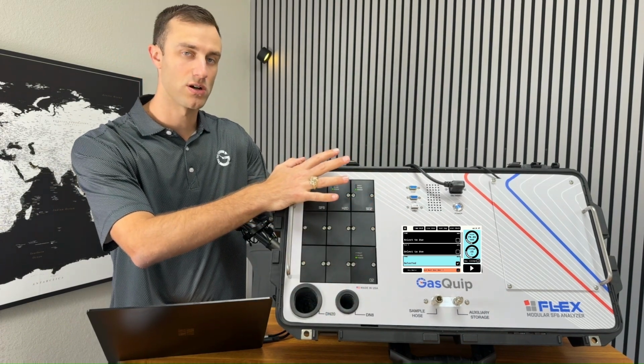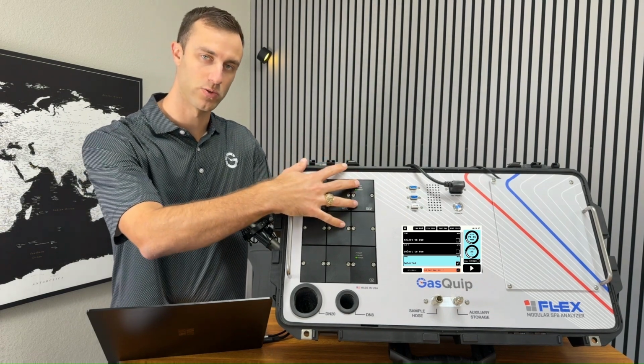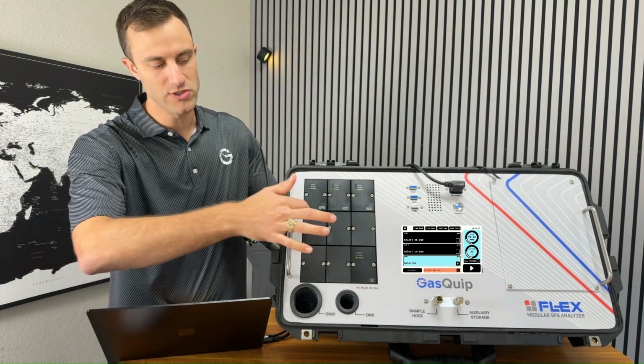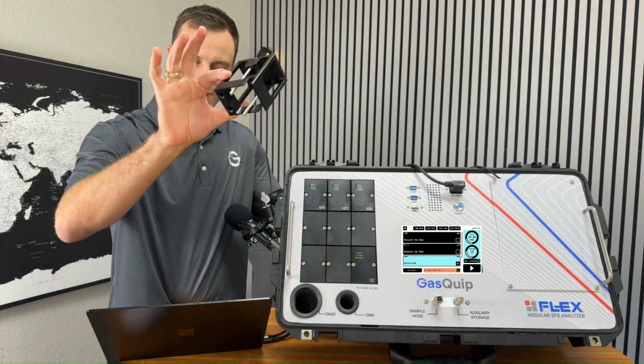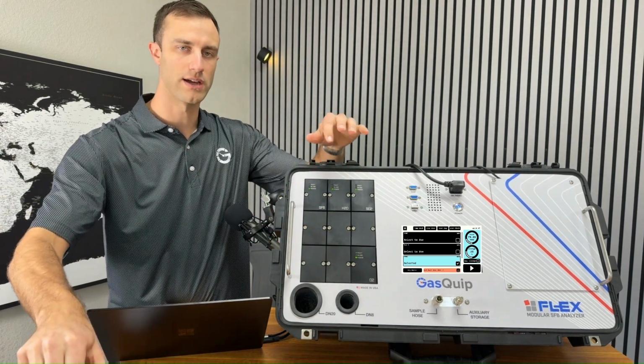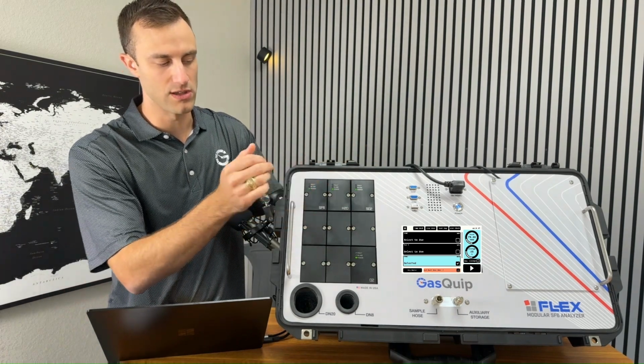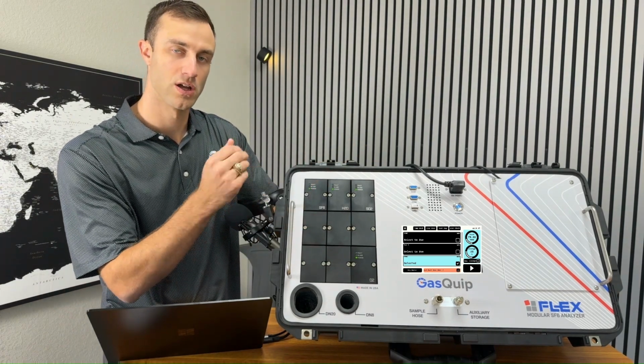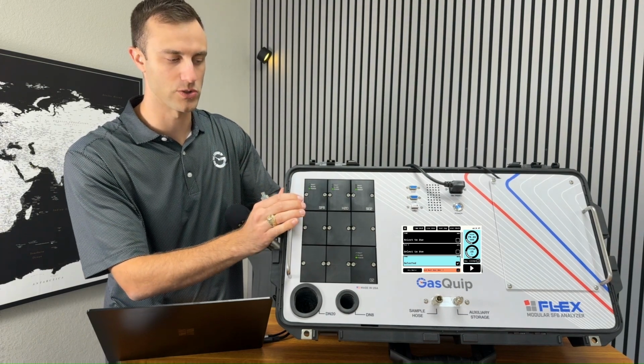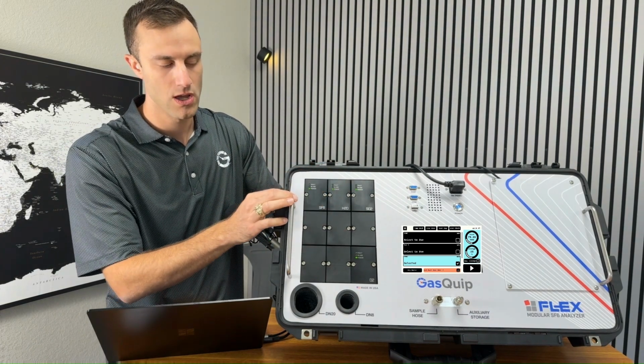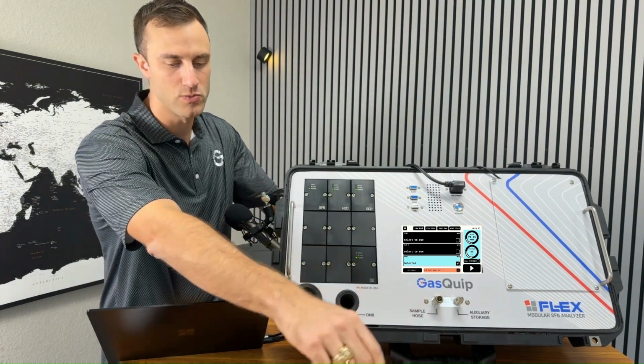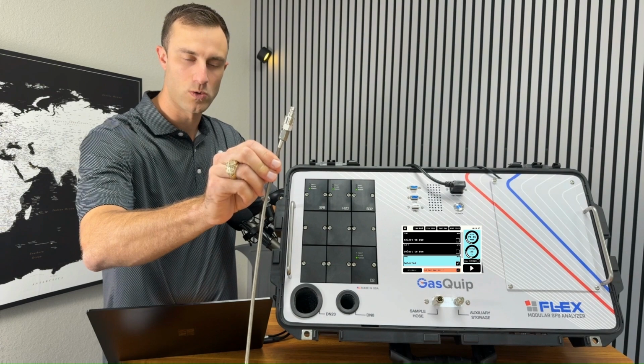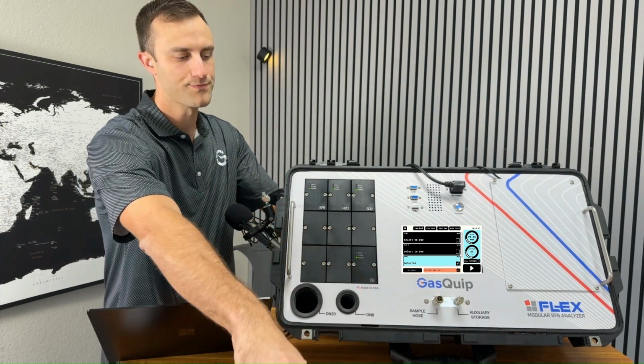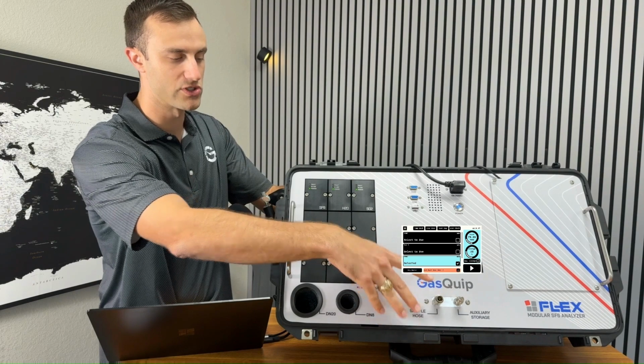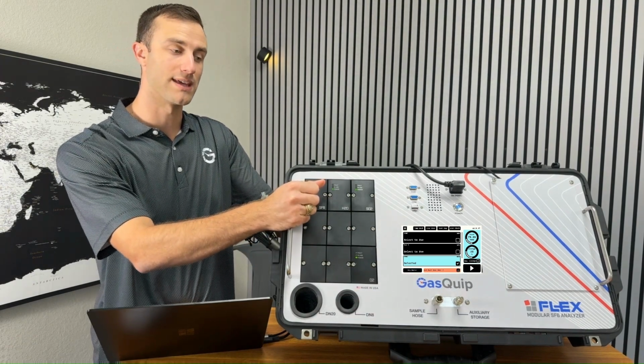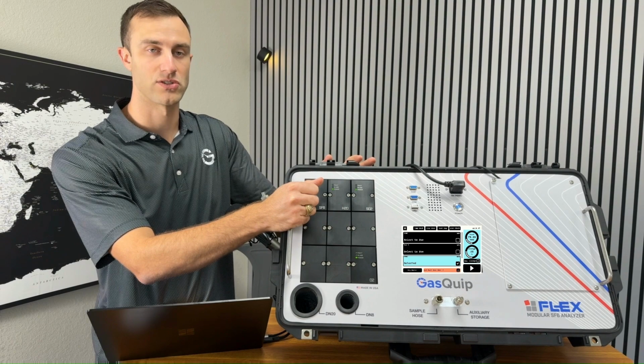Any module can be installed in any of the 9 positions on the module manifold. The empty modules that you see here that aren't labeled are just blanks. They're empty to protect the underlying manifold. And then obviously the sensors are labeled with which contaminant or gas they're measuring on each of the sensor modules. Down here we have the sample hose port that our sample hose will connect to. So that's a male going into the female. Across from that is the auxiliary storage port for connecting up a gas recovery bag or an external cylinder, so just auxiliary storage.